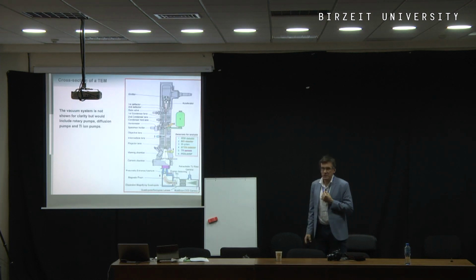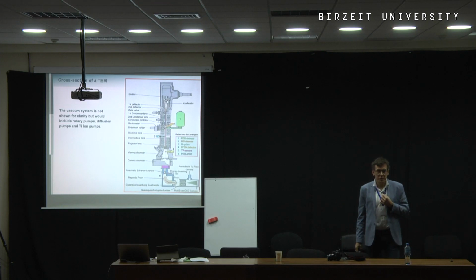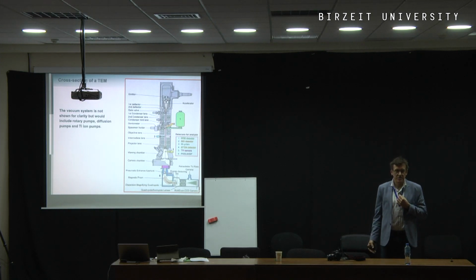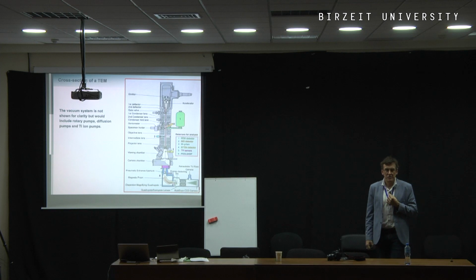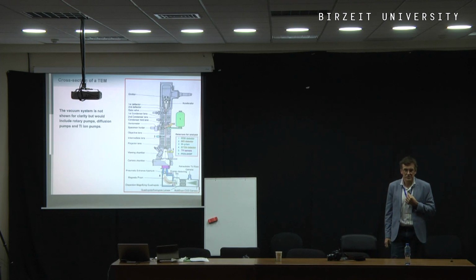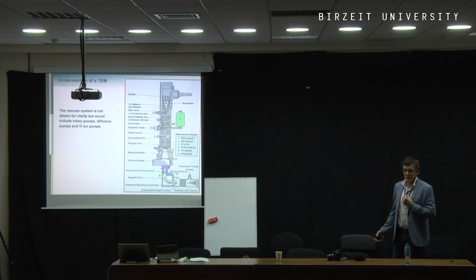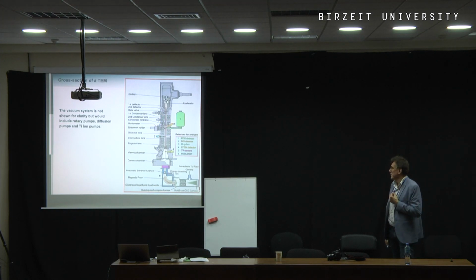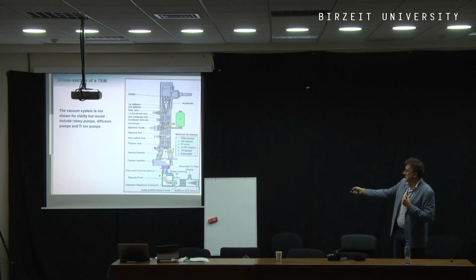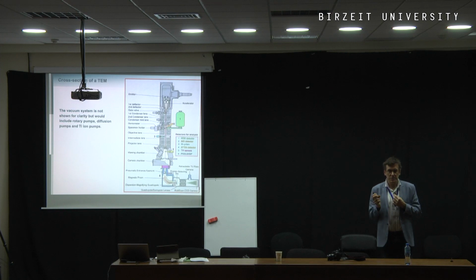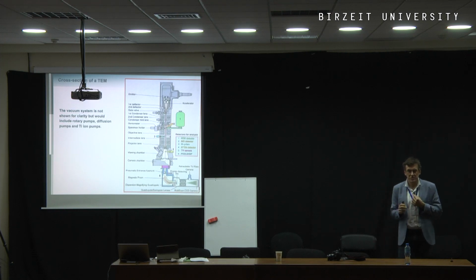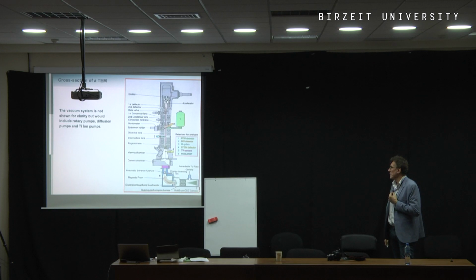So if we look inside an electron microscope column, what we don't see is glass lenses as you would have for light. You have electromagnetic lenses. We don't see much empty space. The electron microscope is full of metallic windings. Each of these windings constitutes one lens. The sample sits roughly halfway up. It's normally very small, only a few millimeters across. And as I mentioned, it can be only a few atoms thick.